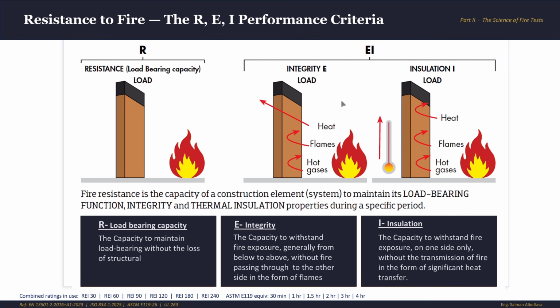And then you can see some certificates with an E and an I with no R. That means these elements don't carry any weight. The fire-rated door does not carry the weight of the building. Its only job is to divide the space and stop the fire from spreading. So the structural performance is irrelevant in this case. But they still contain the fire and keep the other side cool.